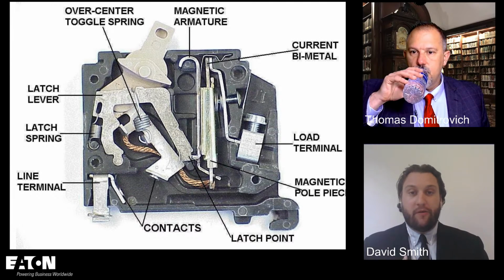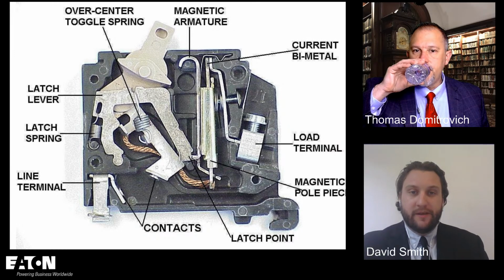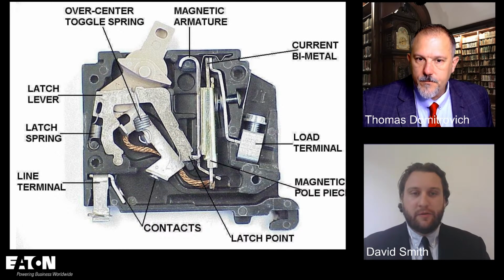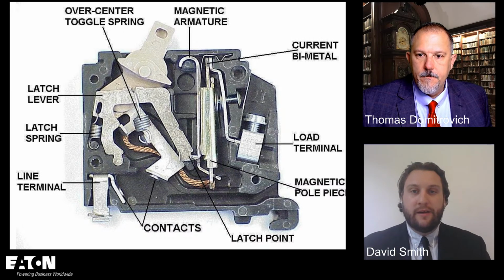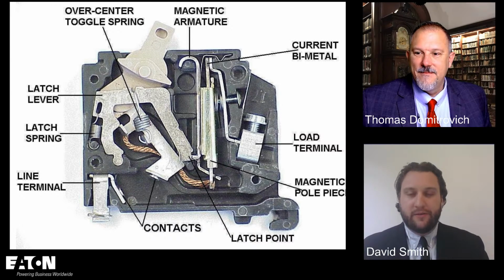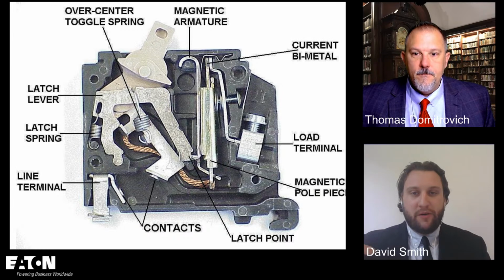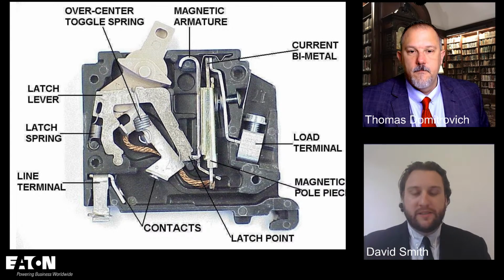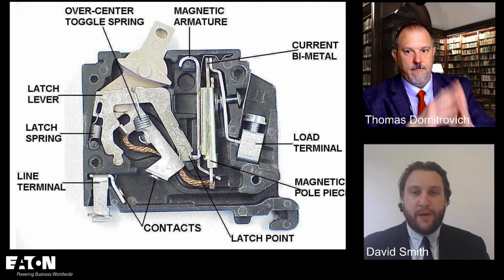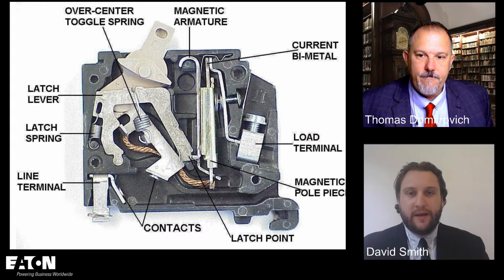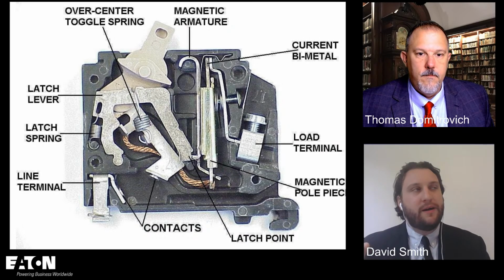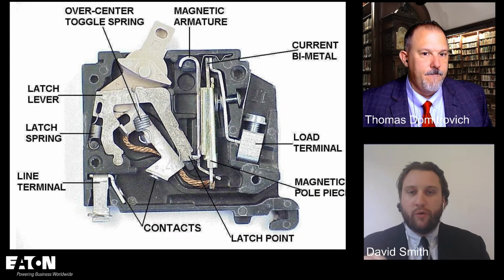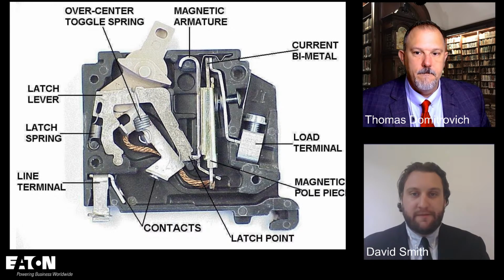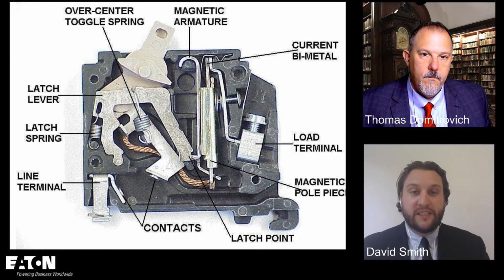Go ahead. The bimetal, this is my understanding of how it works, and you feel free to correct me. With the bimetal, the whole point is that between those two metals, one heats faster than the other. Yep. And as the current continues to go through, once it hits 15 amps or 20 amps, that first metal overheats a little faster and expands more than the other one, to the point where it physically bends, so it trips the breaker. So it's physical, there's not any type of calculation being made, or a processor on the inside or anything like that. Correct. It is a physical bending of the two metals.